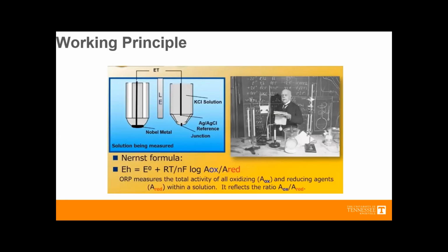This is the trickier part. I'm going to talk about this reference electrode in a second. It's going to have a silver wire on the inside, and a solution of calcium chloride or potassium chloride, or something with chloride in it that is going to provide a stable voltage. So when you make your measurement and hook it up to a voltmeter, one lead goes on here, one lead goes on here, you stick it in the solution, and you make a measurement of one relative to the other. Your voltmeter is going to have a red wire and a black wire. When you're doing this, be consistent with which one gets which connection.